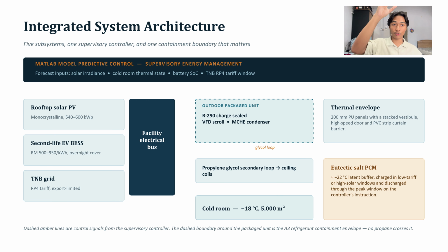So at the top is the controller, the supervisory controller, built in MATLAB. That's the MPC, the model predictive controller. It takes 4 forecasts, which are the solar irradiance, the cold room thermal state, the battery state, and the TNB RP4 tariff. On the left, you can see the 3 power sources: the solar array, the second-life battery, and also the grid. This feeds into the electrical bus.